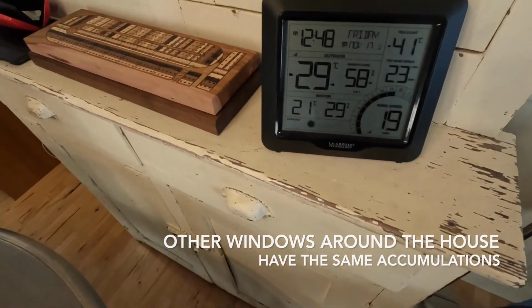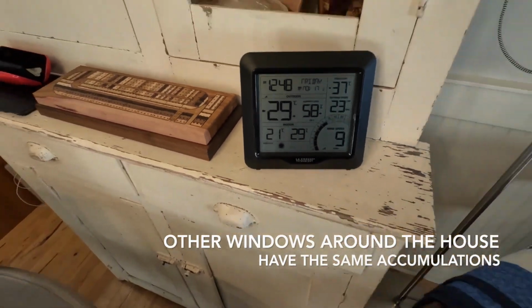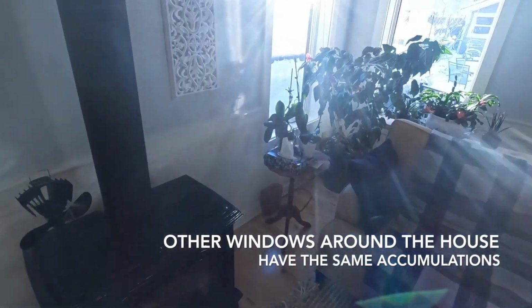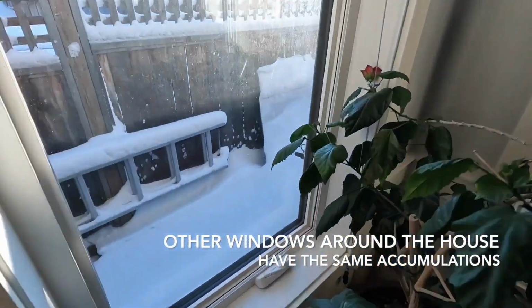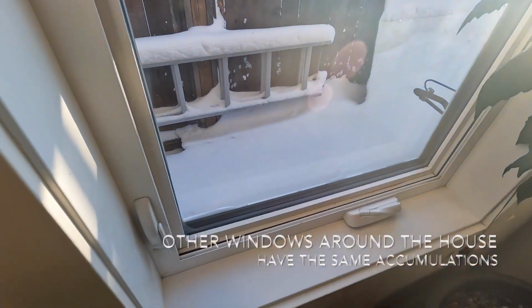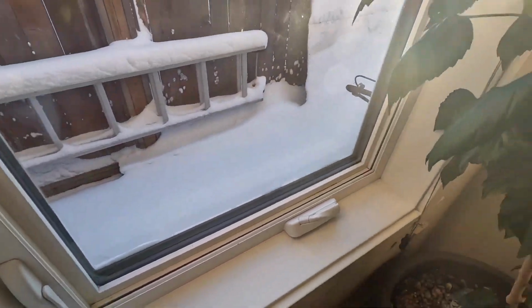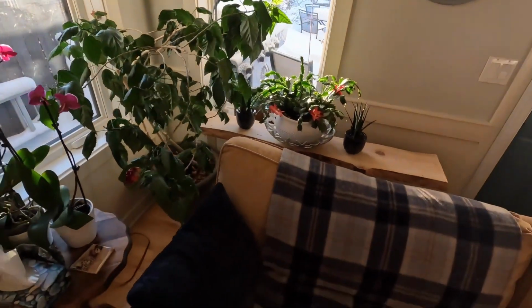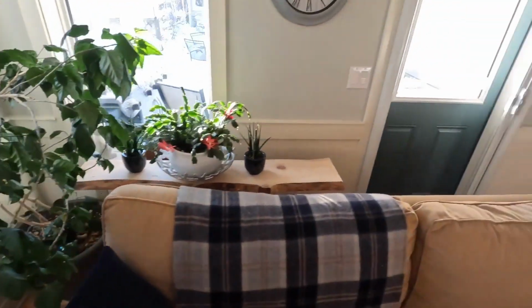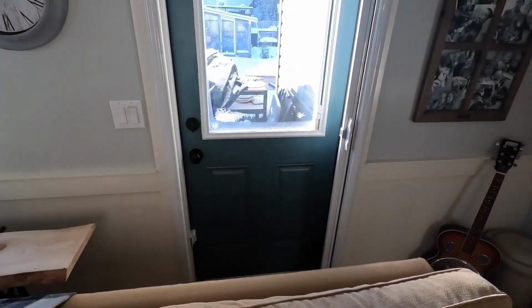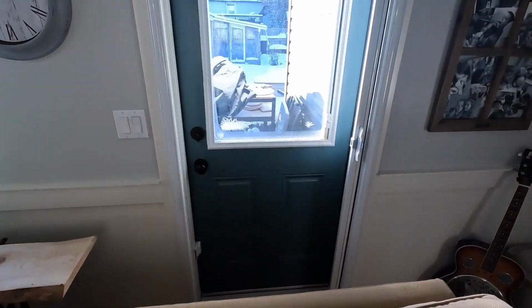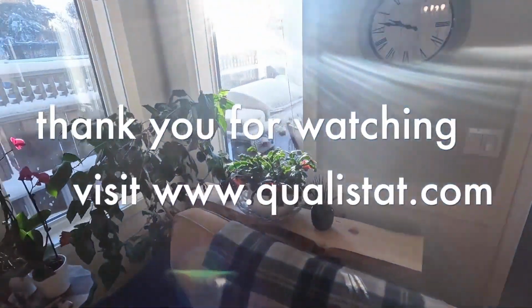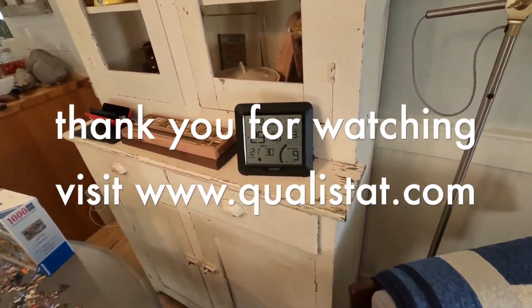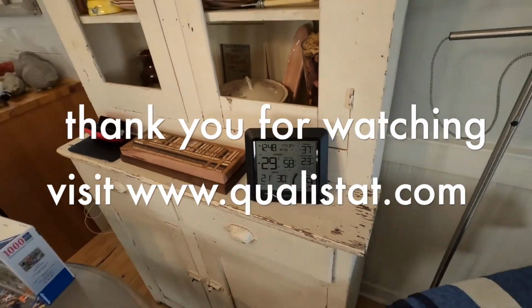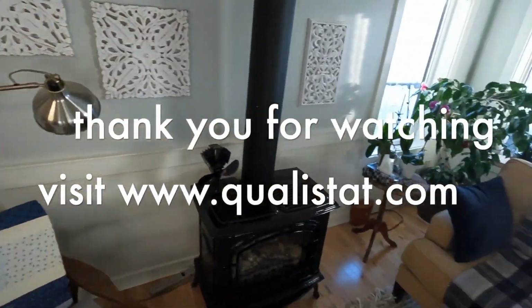Today I've kept the humidity down a little bit, 29%, but you look at the windows, we've still managed to maintain the amount of humidity to a level that it's not really accumulating on the windows too much. We're keeping the fan on, and over here on the glass where there's double glazed, you can see just a little bit of moisture. So managing the moisture on the windows by keeping the humidity just a little bit lower today. And even though it's minus 29 outside with a bit of a strong wind, we're not having too many problems with the windows. Hope that helps.